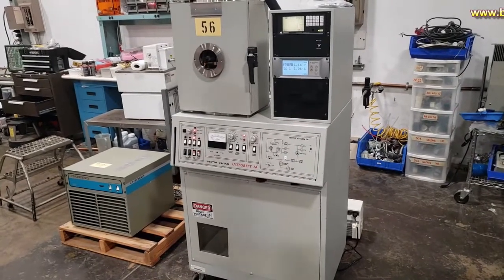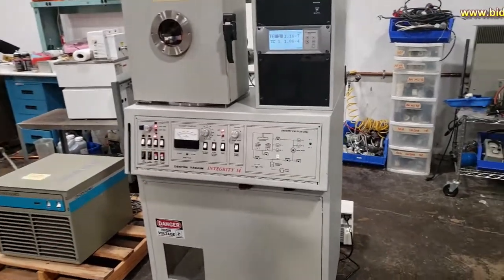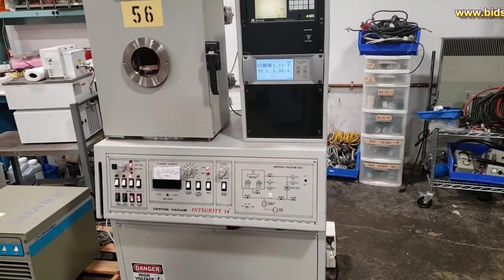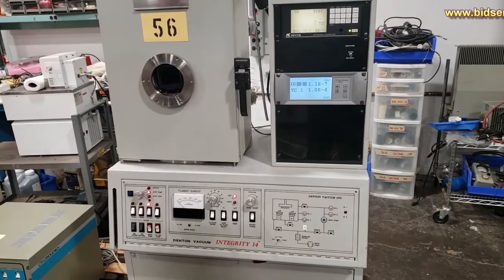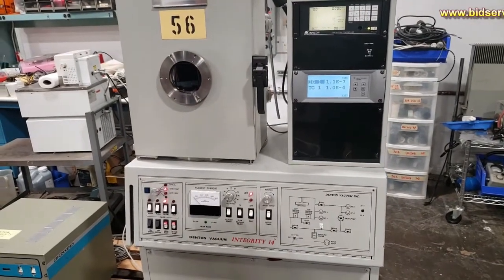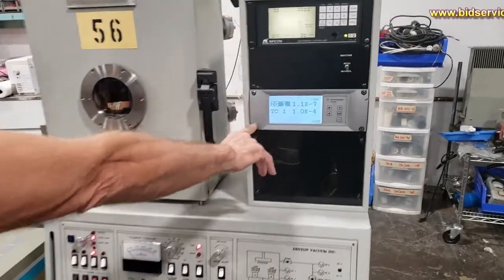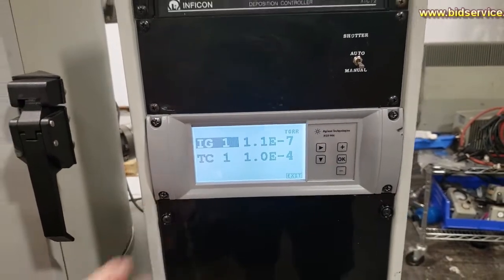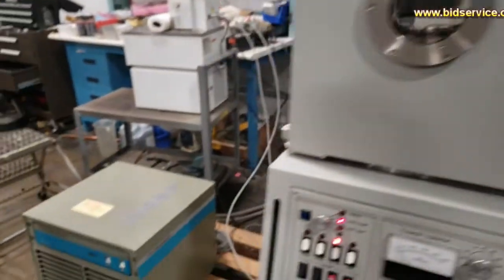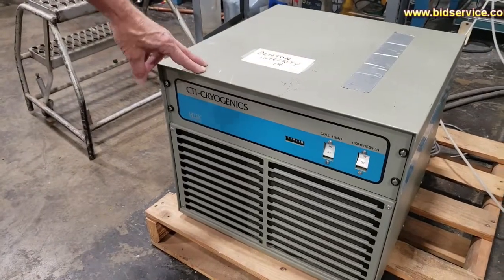This is a video demonstration of the Denton Vacuum, Integrity 14. It's a two-source thermal evaporation system. The first thing to discuss is the gauge controller for your vacuum system. This is a cryo system using an air-cooled CTI-Cryogenics compressor.